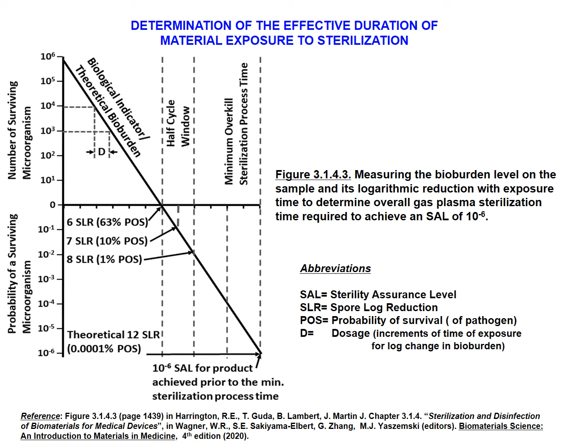As these particular specimens carrying the pathogens are exposed to sterilization, and then we determine the number of viable microorganisms, we find that there are fewer and fewer cells which are viable, and if we plot those points, we get a straight line which is cutting diagonally on this graph. When that line cuts the x-axis at the 10 to the minus 6 point, which is the sterility assurance level, that time point is the length of time needed in order to expose a specimen to the sterilization process under consideration, and this time point is expressed in minutes.